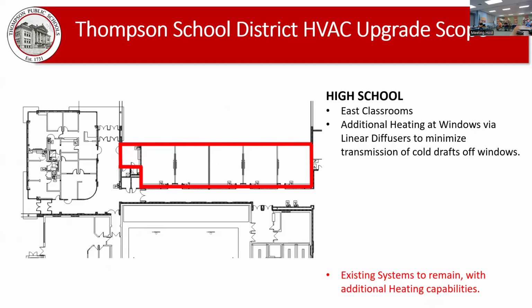The intention here is to utilize the existing systems as they are, utilizing the existing rooftop unit, but provide supplemental heating through linear diffusers at the window curtain wall. So we can wash that wall and add additional heat within the space to take the cool draft off of that, allowing the base building system to be more effective.